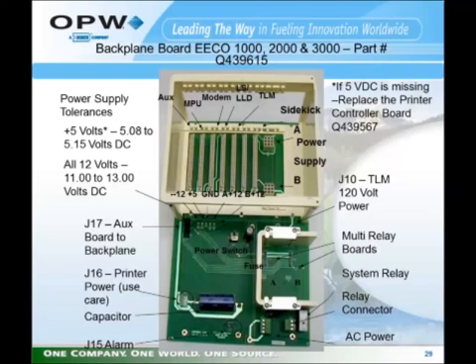Below the card cage are test points where you can check the voltage outputs of the main power supply: 5 volts, 12 volts A, 12 volts B, and ground, and negative 12 volts. The 5 volts is normally adjusted to a level of 5.08 to 5.15 volts, nominally 5.1 volts DC. That is a regulated output. The 12 volt outputs are not regulated and normally between 11 and 13 volts DC.